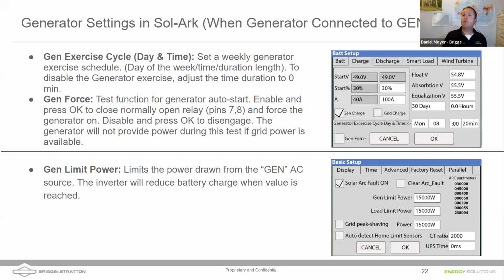And if it doesn't, it's going to throw a fault code and make sure you get a service person to come out. Another reason why you might want some generators to come on is so that it can charge up its internal battery. Like I said earlier, we're using a grid source to keep our battery charged. So we use our generator auto exercise, frankly, just to make sure that it's going to work when you need it. Now, that can either be controlled out of a Sol-Ark, or it can also be controlled on the controller inside the generator.